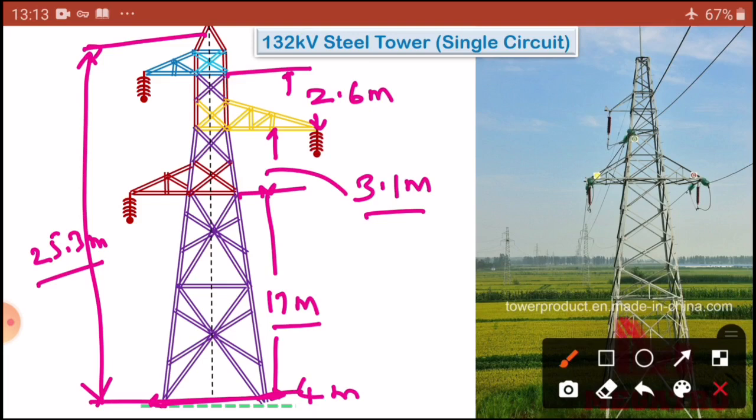Now at the same time I am going to find what is the length from this place to this place. Because it is a ground, this is live, it acts as a capacitor. So what is the distance we have to maintain? This is nearly 3.9 meters gap from center to here, so 3.9 meters. Okay, so that is the distance.